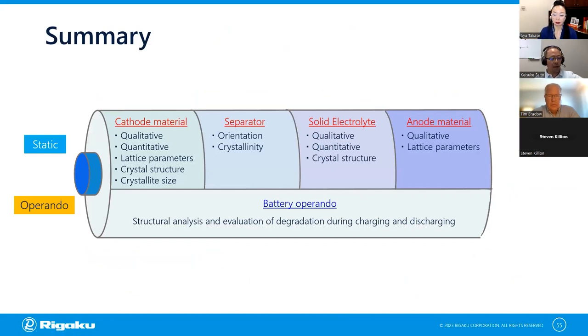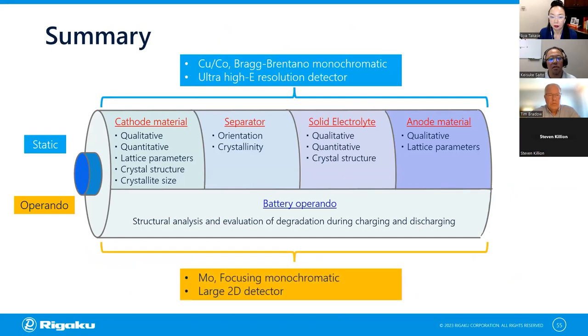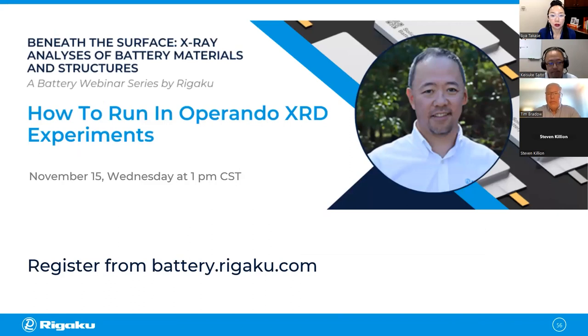Let me conclude. For static measurement, the best configuration is copper or cobalt X-ray source combined with Bragg-Brentano monochromatic beam and ultra-high energy resolution detector. For operando measurement, molybdenum is the best choice combined with focusing monochromatic beam for better transmittance, combined with as large a 2D detector as possible. Thank you very much for your attention. We have time for one or two questions.